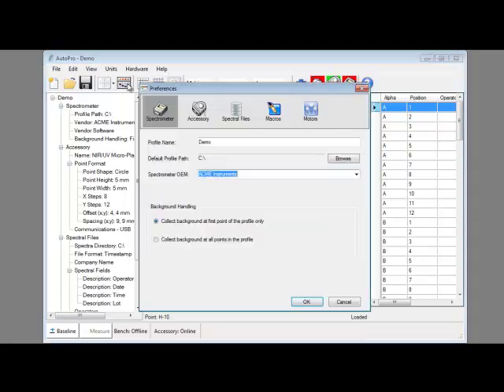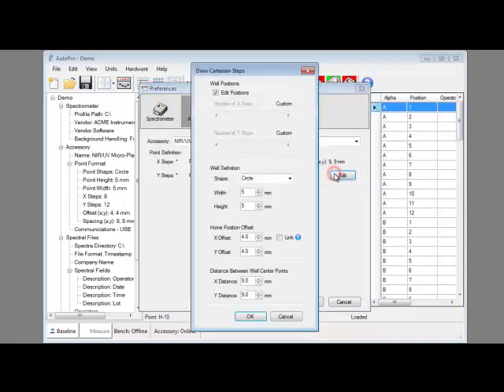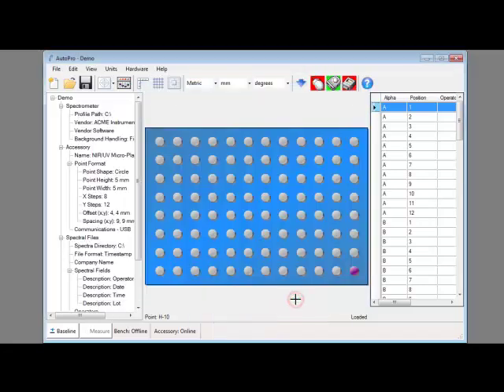Key setup steps include selection of the instrument, accessory selection, selection of the microplate type, entry of the operator and sample details, and initiation of the measurement.